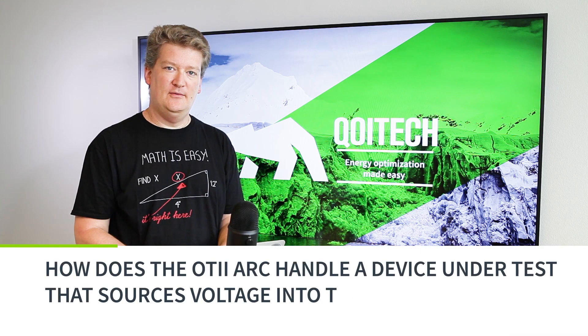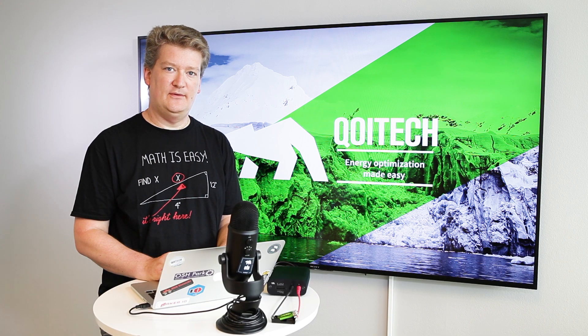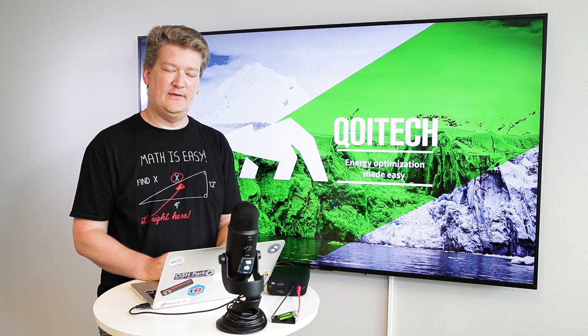Hi, it's Werner from Qoitech again. You asked us if it's safe to connect the voltage source to the Otii Arc main terminals when the ARC itself is in the default voltage source mode. In general, this is safe as long as the voltage applied is below the five volt maximum.